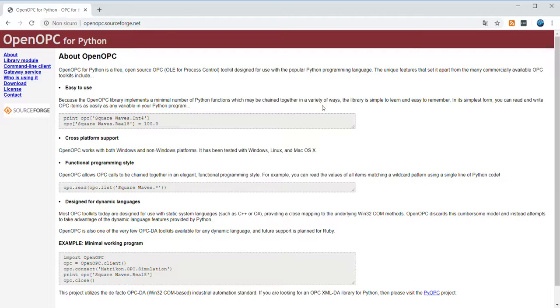So how things work exactly, but it's not so complicated to do, and this is the way for achieving this non-trivial task of reading from a Node-RED flow that is installed in a Linux host, reading from an OPC server that is by definition installed on a Windows host, because the communication is done through DCOM, that is a Microsoft technology.